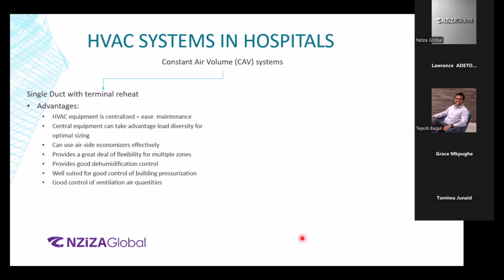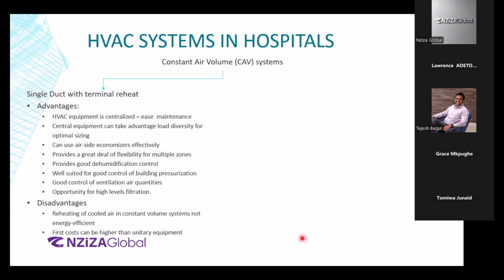Dehumidification can be done properly, well suited for good control for even the ventilation air strategies, and there is an opportunity for high level filtration. Talking about disadvantages, reheating the cooled coil. Cooled air is not energy efficient, but if you need to maintain certain leaving air temperature out of the duct, we need to do this. First cost is higher as compared to a unitary system, and requires mechanical space in the mechanical equipment room as well as shafts. Now, we'll talk about the dual duct.